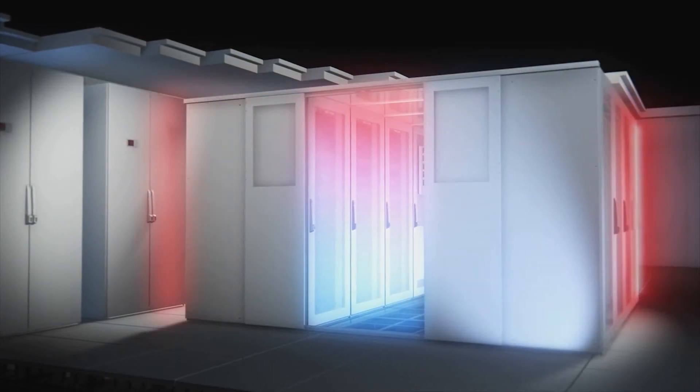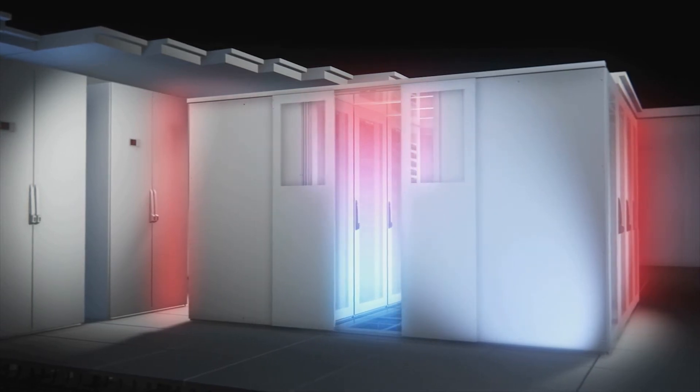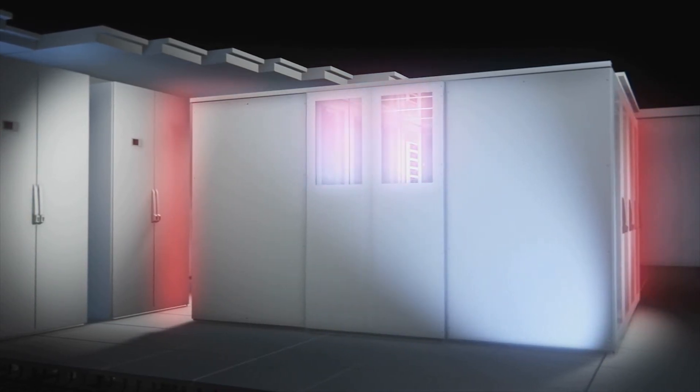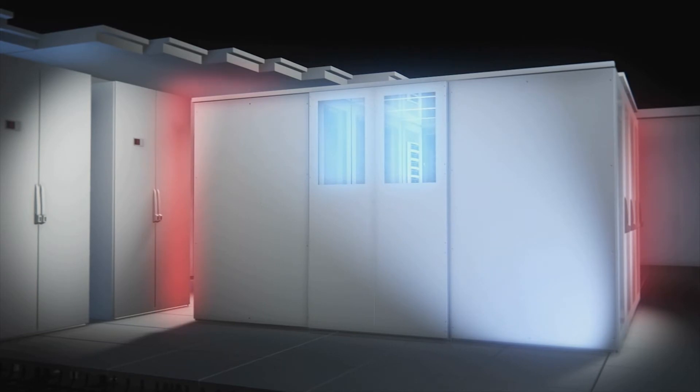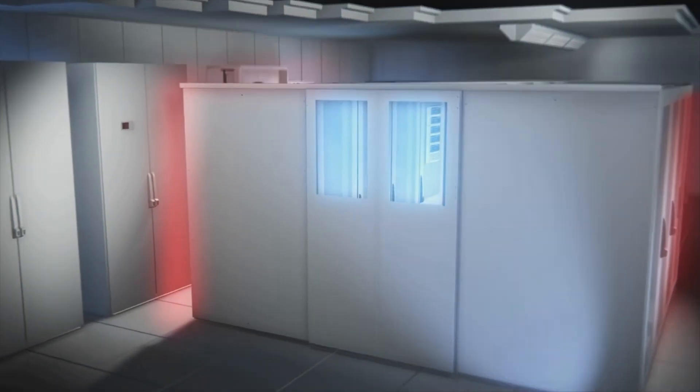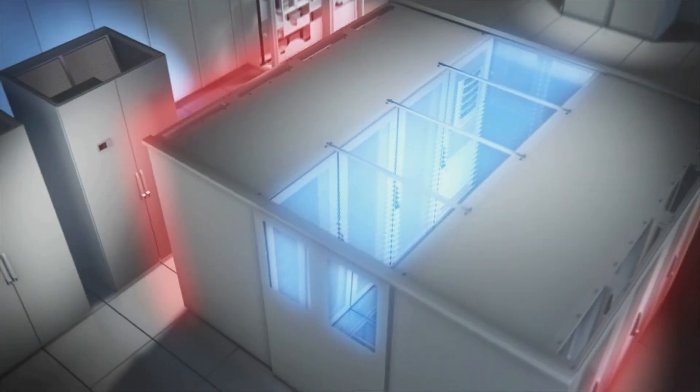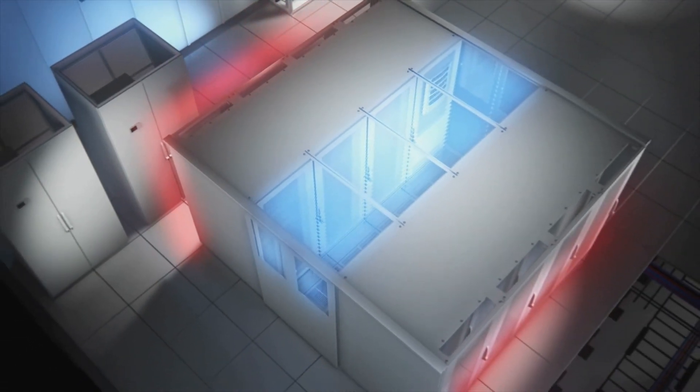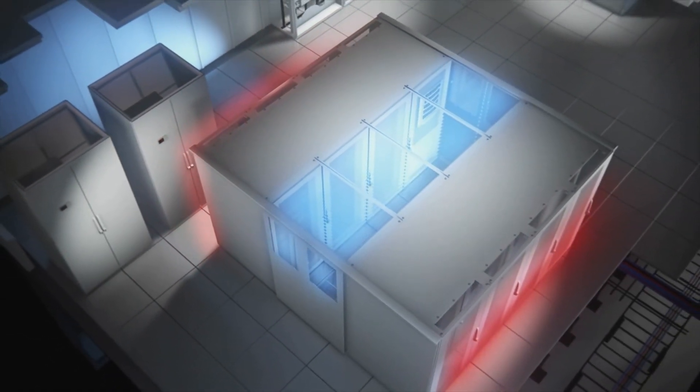Even with this basic array, you can enhance the efficiency and performance when you contain the air within a row of enclosures. Separating hot from cold air boosts efficiency. Cold air stays in front, warm air stays in back, and they don't mix anywhere in the room.